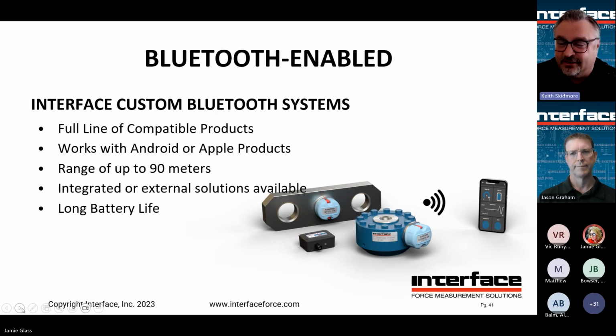So you can imagine in a test lab, you probably don't want all the data going into somebody's phone - you want it into a data acquisition system. So this might not be useful there. Now if you're doing some kind of device where you just want somebody to walk over with a phone and check the level of a tank - say barbecue grills, checking how much gas is in the tank - Bluetooth would be perfect for that. So it has its place. It doesn't have quite as much range, but it does have a lot longer battery life because of that, since it's not transmitting with such power. Some OEM solutions require Bluetooth, for example. So keep in mind Bluetooth is available, but it's not necessarily ideal for industrial type applications.